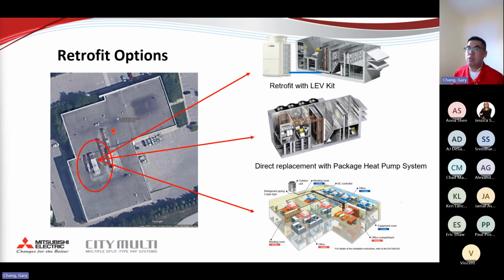Let's retrofit it with what we call an LEV kit. That means we're taking out the DX coil inside and removing the condenser fan from the existing units, but retaining the belts, the fans, the controls, the thermostat, everything. We simply replace the internal cooling coil with a VRF coil to still meet that ever-changing temperature. This is a popular design.